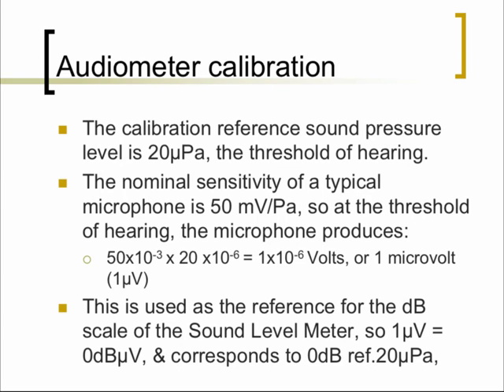Moving on with electro-acoustical calibration, a little more information about how the sensitivity of the microphone used on the SLM is determined. The calibration reference sound pressure threshold, what we call the reference equivalent threshold, is 20 micropascals, which is considered the threshold of hearing.